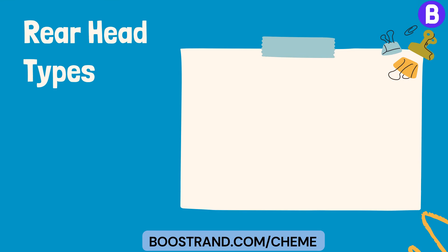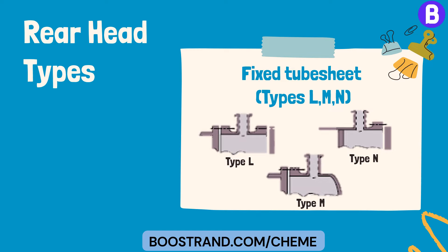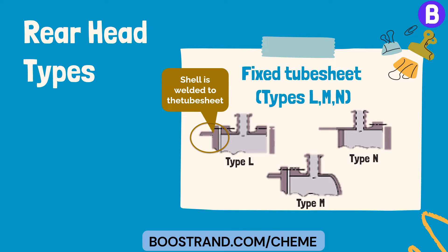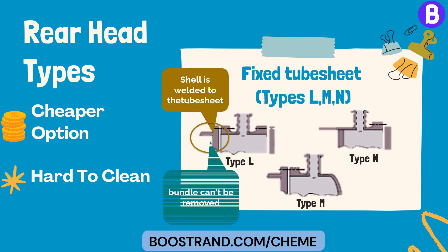Now let's talk about rear head types. Fixed tube sheet, Types L, M, N: these designs feature tubes fixed to tube sheets welded to the shell. It's a cost-effective option, but cleaning the outside of the tubes can be challenging as the bundle cannot be removed.